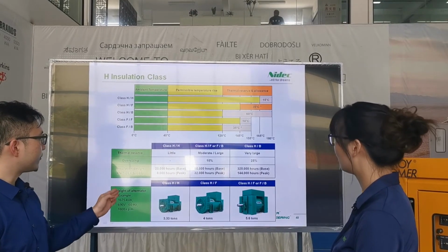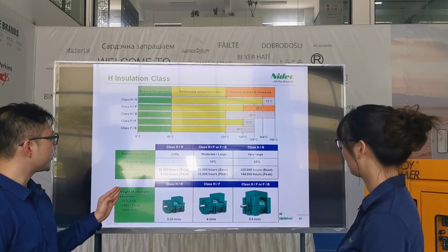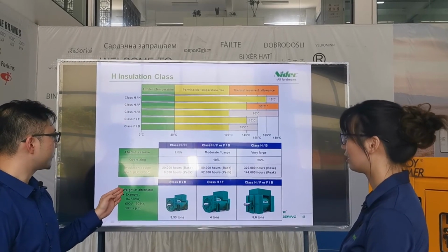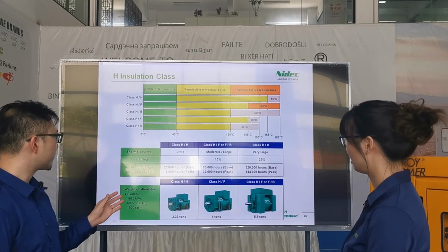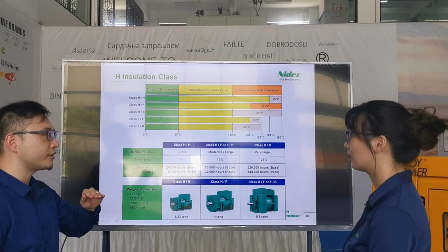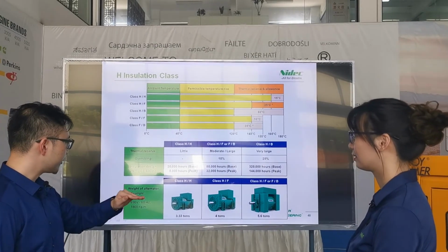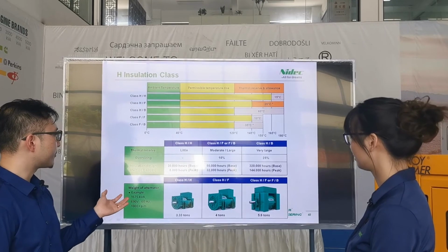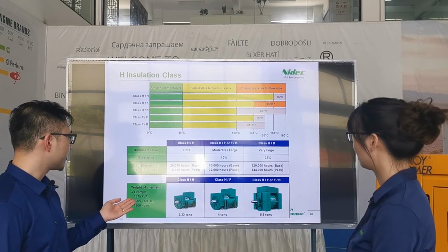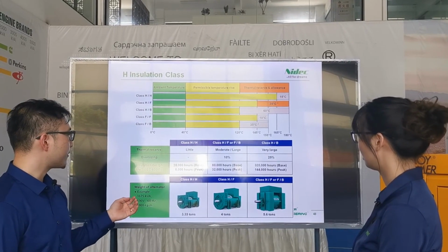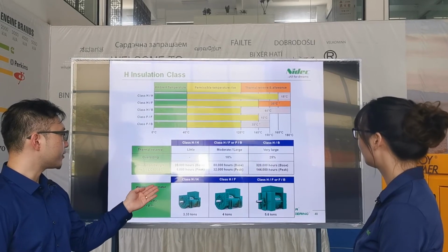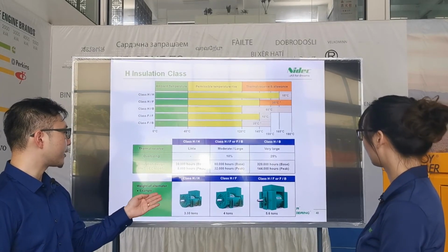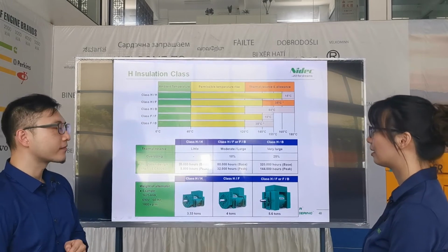Also, with different insulation class and temperature range class, the weight of the machine — even at the same power level, voltage level, and speed level — will be much higher. For example, if HH is 3 tons, HF will be 4 tons, and HF or FB will be like 5.6 tons.